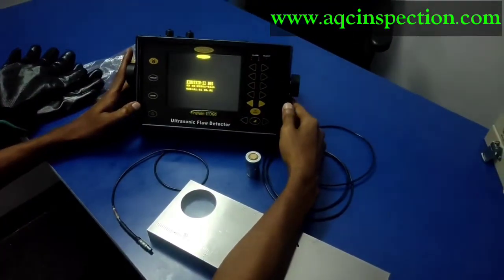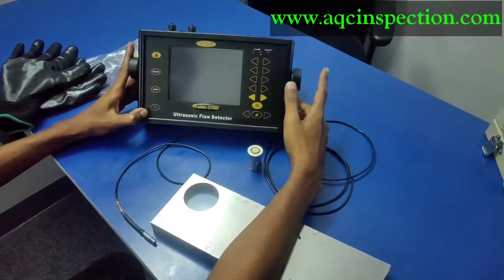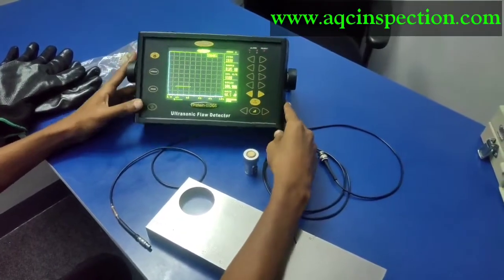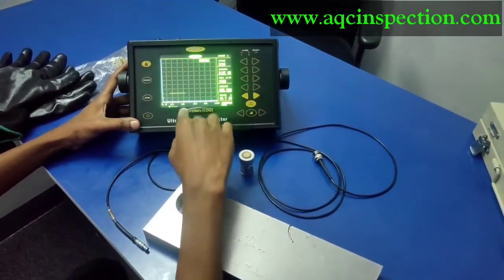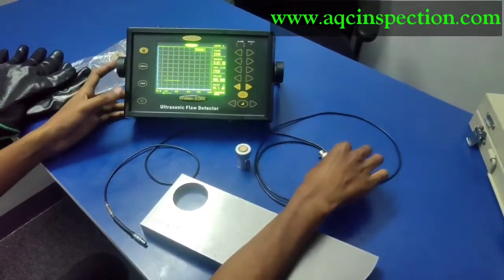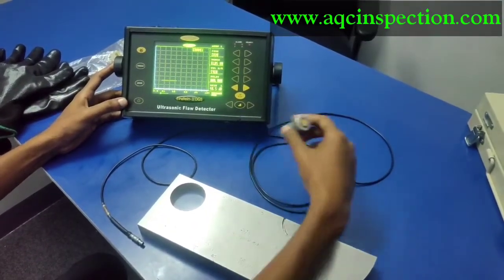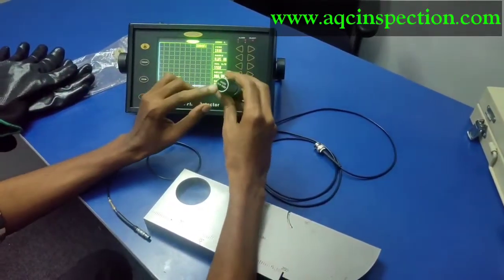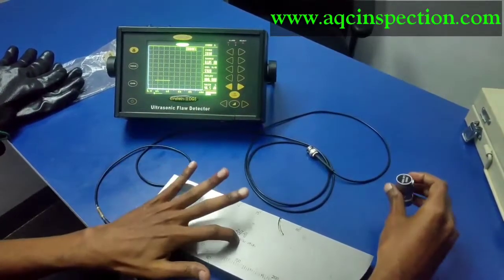This right here is the ultrasonic flaw detector which we are going to use for this calibration. This model is Modsonic Einstein II DGS, it's an Indian make model. We are going to see the calibration of a normal probe which is a 10 mm diameter crystal, 4 MHz frequency using V1 block.